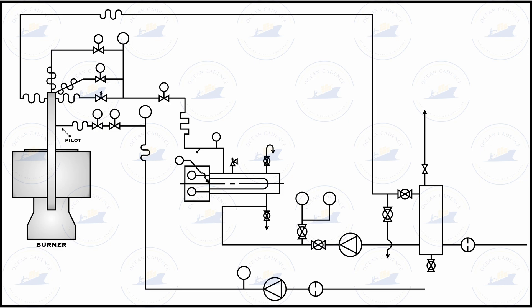To initiate combustion, we have to make sure that the pilot burner fuel oil is supplied through a separate line. Generally this line consists of diesel flow because it is easier to ensure the start of combustion on diesel oil. That is why the line is kept separate. It has a separate fuel pump, individual pressure gauges in the line, a separate strainer, as well as separate solenoids for the auto-triggering of the initiation of combustion.